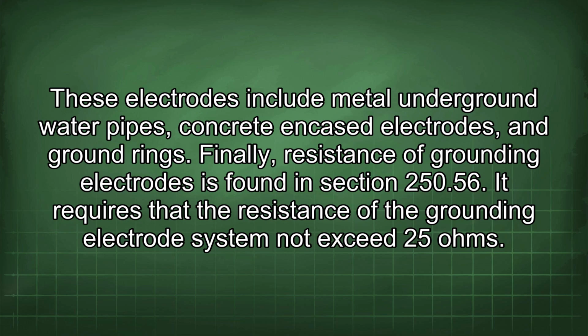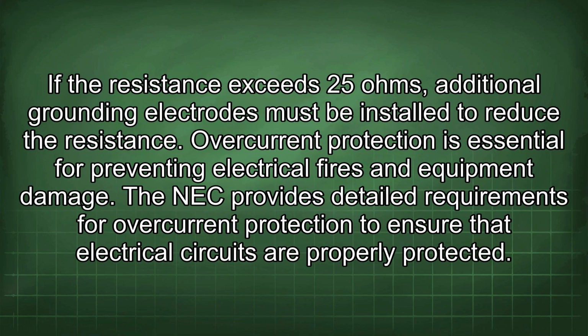Finally, resistance of grounding electrodes is found in Section 250.56. It requires that the resistance of the grounding electrode system not exceed 25 ohms. If the resistance exceeds 25 ohms, additional grounding electrodes must be installed to reduce the resistance. Overcurrent protection is essential for preventing electrical fires and equipment damage. The NEC provides detailed requirements for overcurrent protection to ensure that electrical circuits are properly protected.